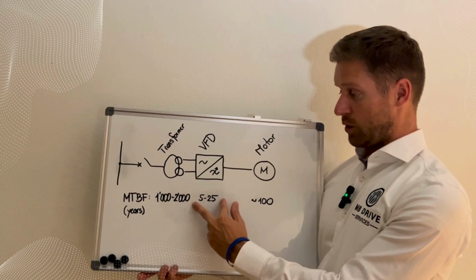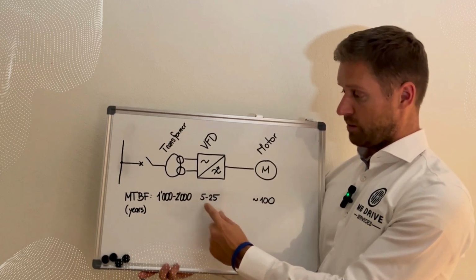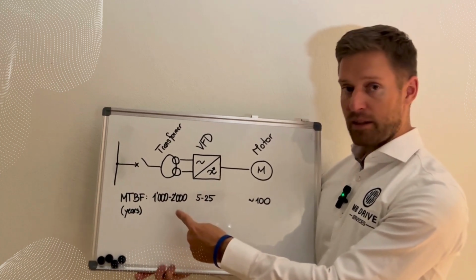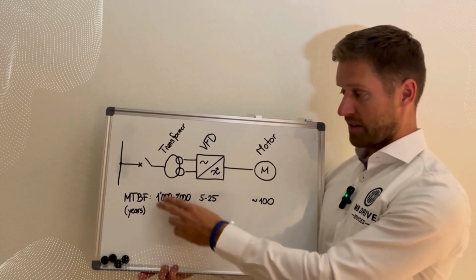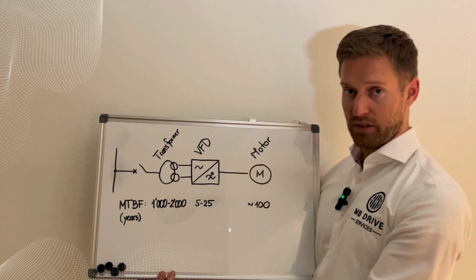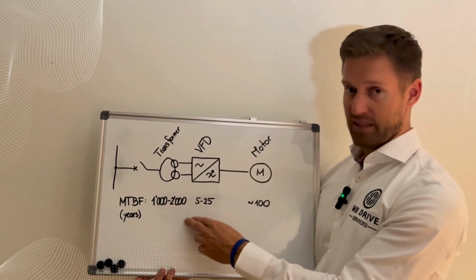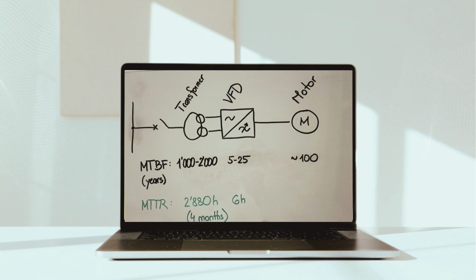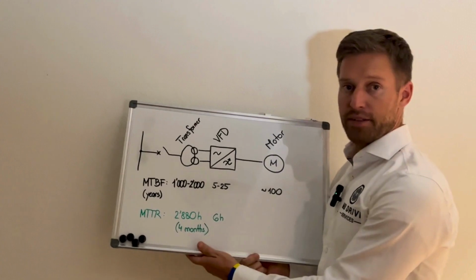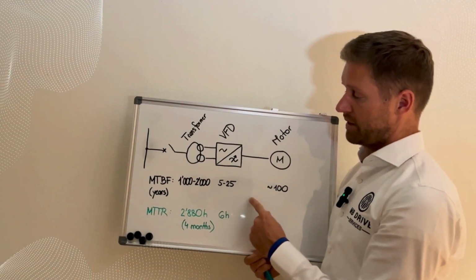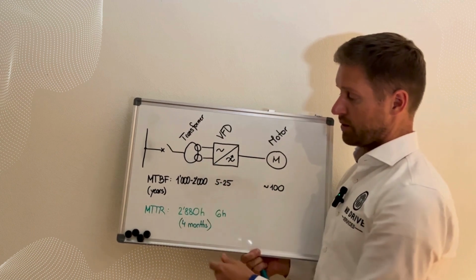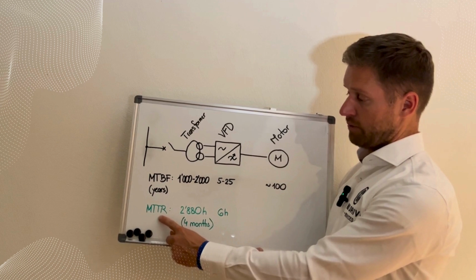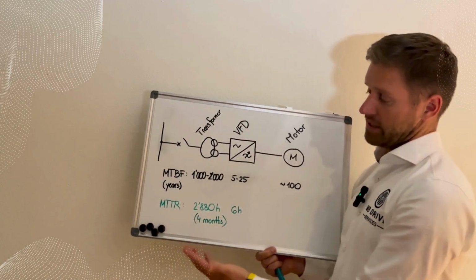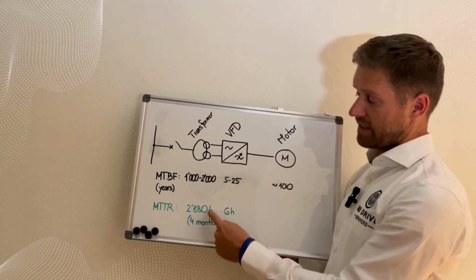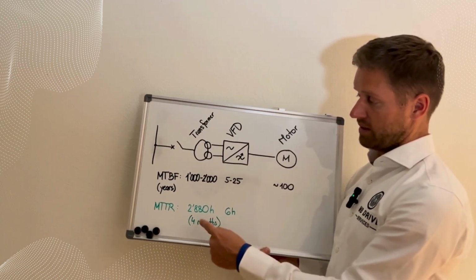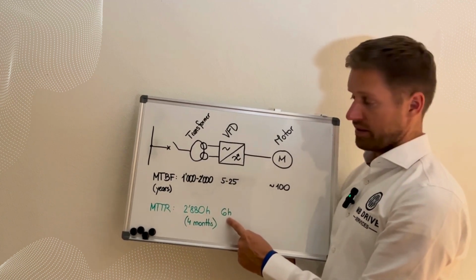On the VFD it looks very low compared to the transformer, but this is where I see that the MTBF is not the only figure you should look at. There is also the MTTR, so let's look at the MTTR as well. Here we still have the MTBF figures, those numbers of years, but let's look at the MTTR. For the transformer I put here as an example 2880 hours, which means 4 months. And for the VFD I have 6 hours.